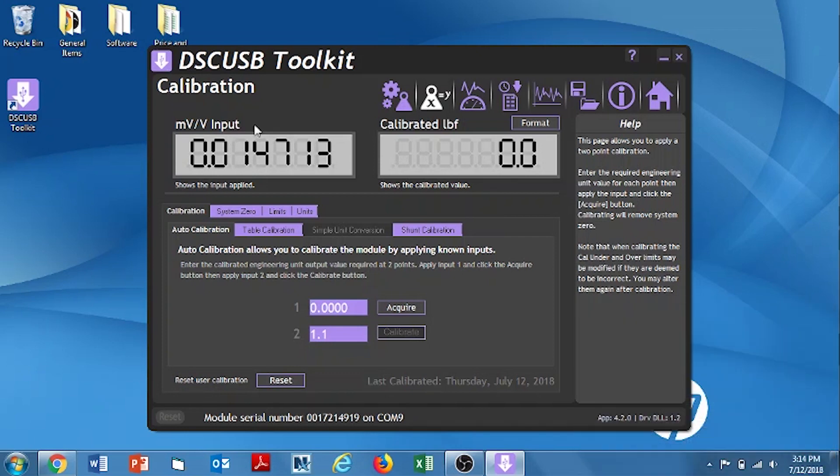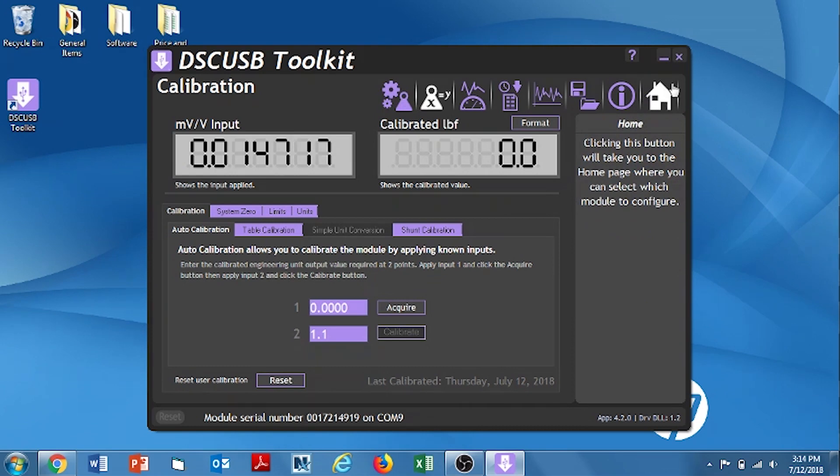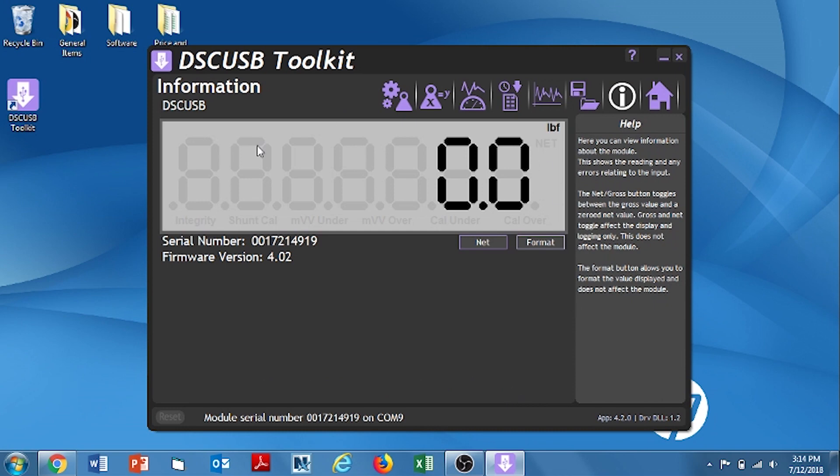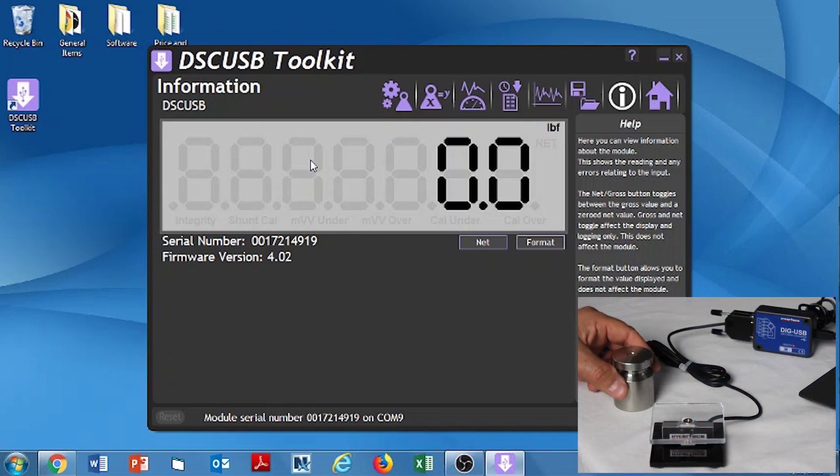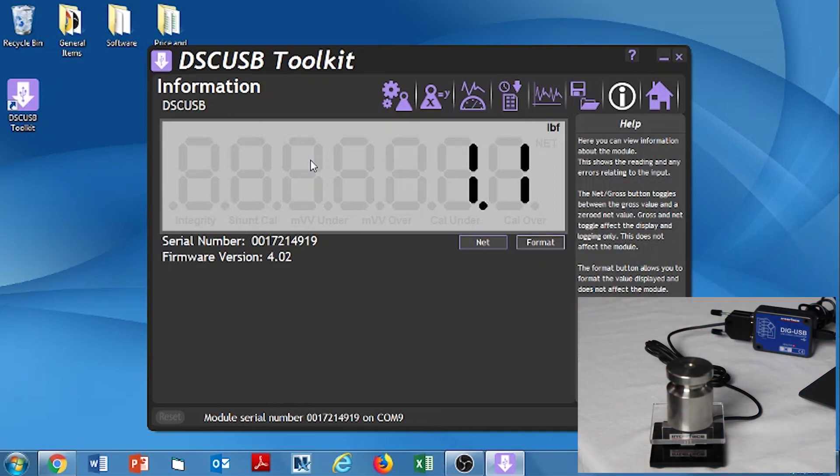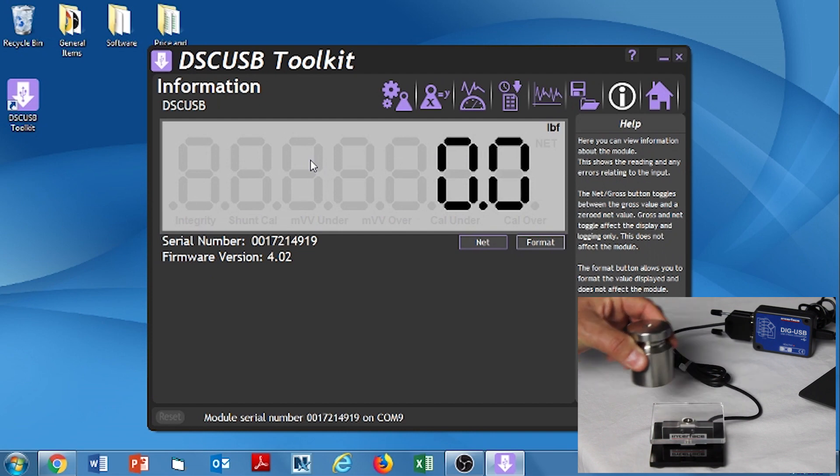Now we're going to go back to the home location, where the picture of the house is. The serial number of the unit should be showing. And then we're going to click on it, and then click Connect. That takes us back to the large screen that we were showing at the beginning. And now we can run a test to make sure that when we load our 1.1 pound weight onto the scale, that we get that reading. We'll do that right now. There we go. We've calibrated it, and we've verified it. You're now good to go.